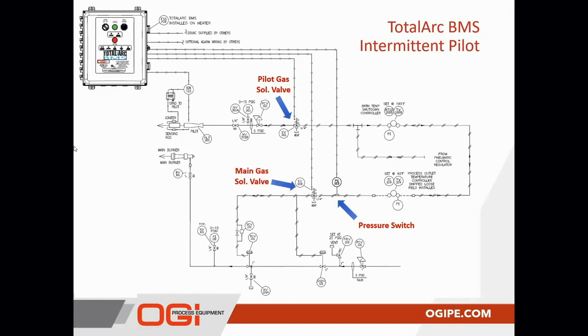When the call for heat or the heater pneumatic safety is lost, the BMS control pressure switch will drop out and the pilot and main burner solenoids will be closed, shutting down the pilot and the main burner, just as we did in the previous version. Once again, though, when the bath cools, in this case, instead of just lighting the pilot, it will actually light the pilot and the main burner under an intermittent operation. So the significant difference between the two is the fact that the intermittent pilot means that the pilot is only on when there's a call for heat.